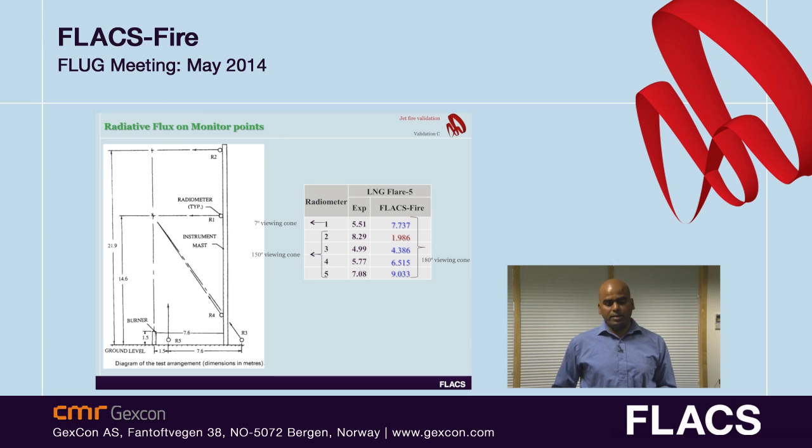Also we have compared the radiative heat flux measurements and the FLACS-Fire simulation. This shows the FLACS-Fire predicted heat flux at different monitor points. For monitor points 1, 3, 4, and 5, there is very good agreement between the experiment and the FLACS-Fire simulation.